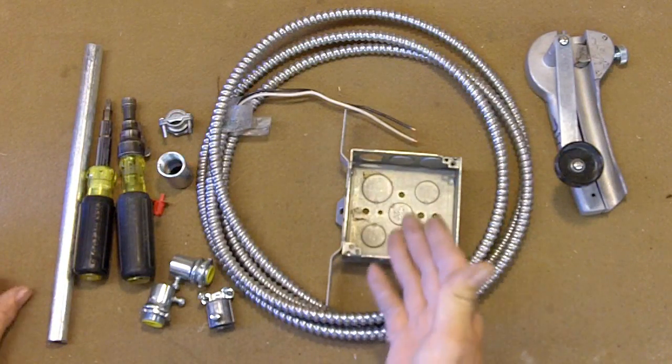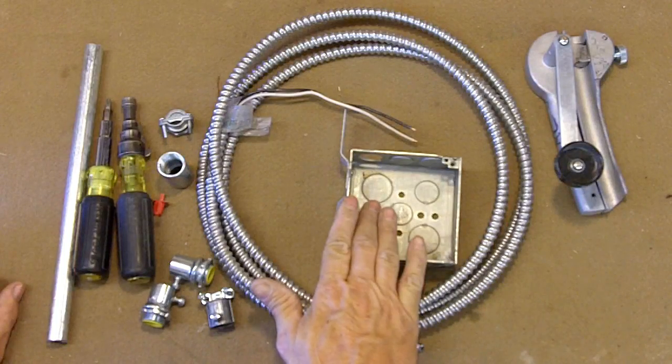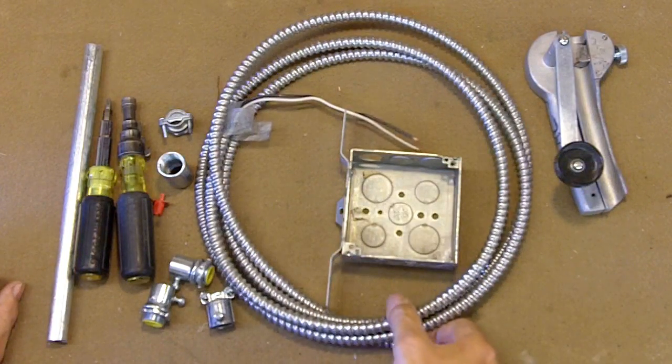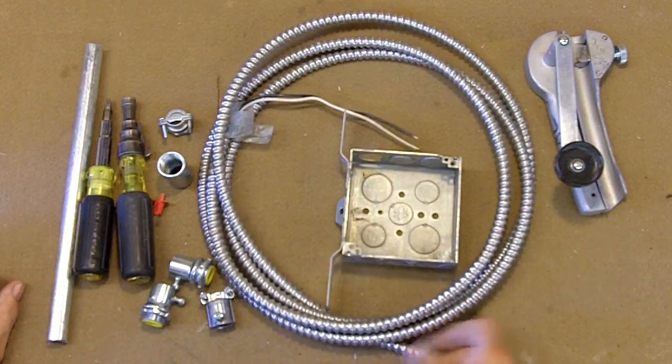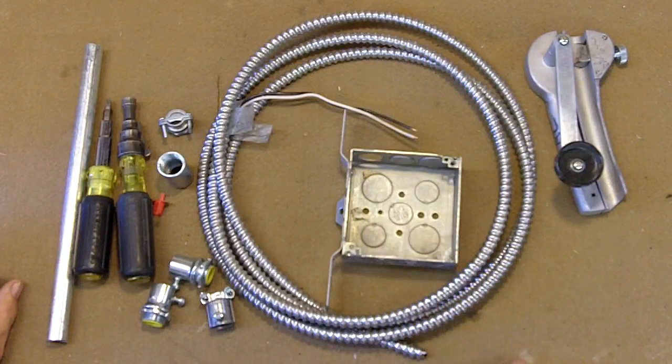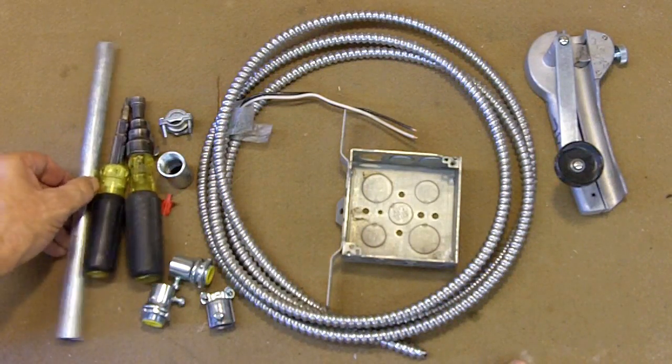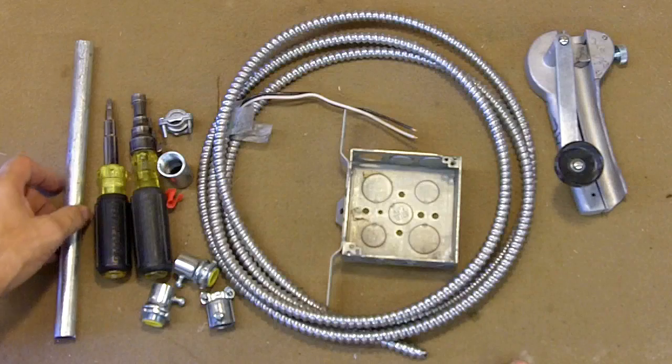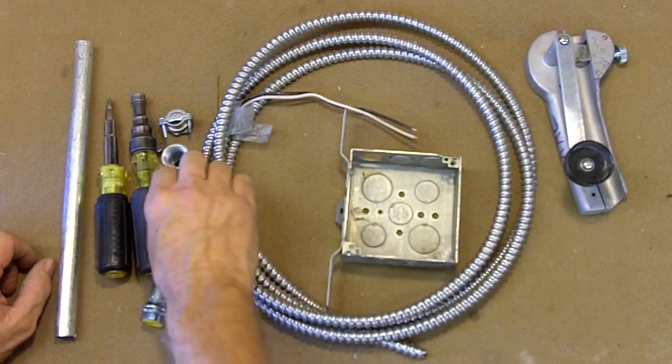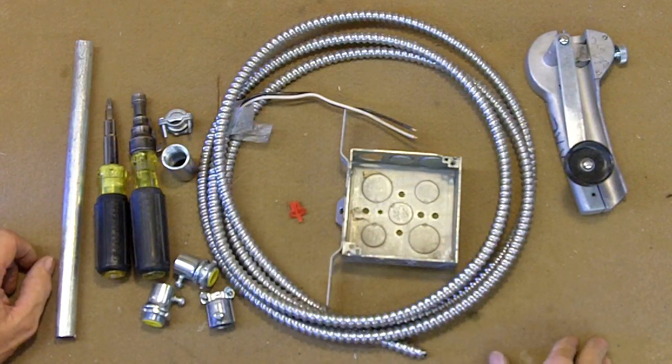Basically you're going to have your box which is probably mounted up against a stud and in this case I've got some 12/2 MC here. Got just a short piece of pipe just for the demonstration.